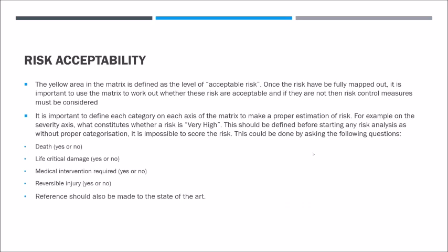But again, if you've got a device where, in the state of the art, there is an accepted risk of death of low percentage, then even answering yes to that question doesn't necessarily make your device fall into the highest severity category. It most likely does, but it depends on the state of the art in the market. Then you can ask whether it can cause life critical damage, yes or no. Medical intervention required, yes or no. Reversible injury, yes or no.